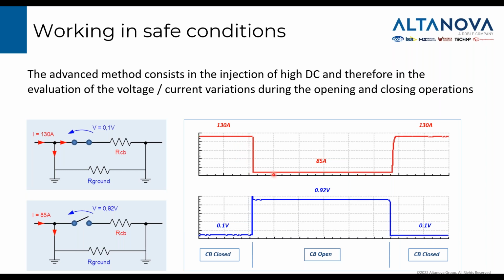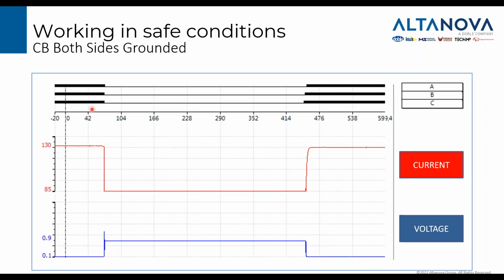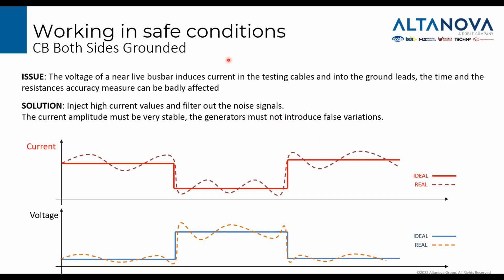Here is when you open the breaker, and here you close the breaker. So if I make an analysis of this signal, I am able to understand when the circuit breaker is opening and when the circuit breaker is closing. But this is an ideal situation. This is a simulation, so it's very easy to perform the measurement if you are in a laboratory. But when you are in the field, the situation is extremely different.